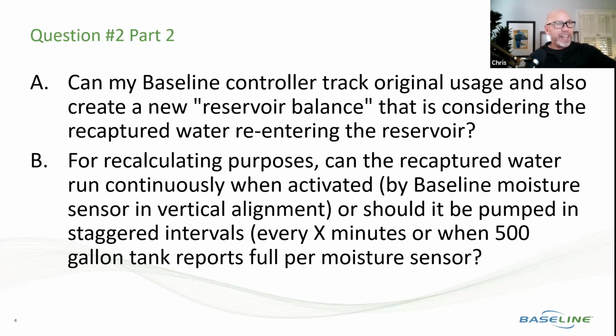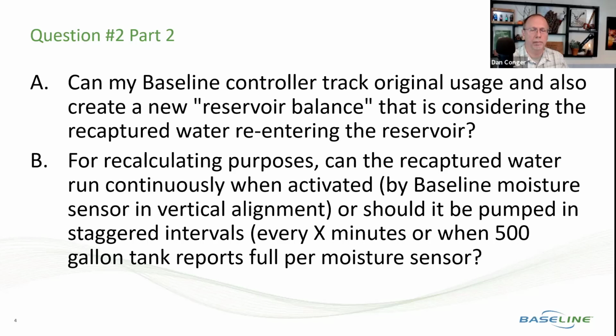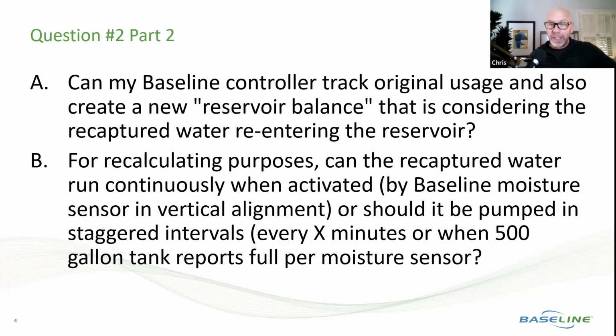So in this case, baseline moisture sensors in a vertical alignment could be a great level indicator in a tank or cistern. But we found that the ability to read the 4 to 20 milliamp decoder, working with a pressure transducer, is a much more elegant solution and can be more accurate.